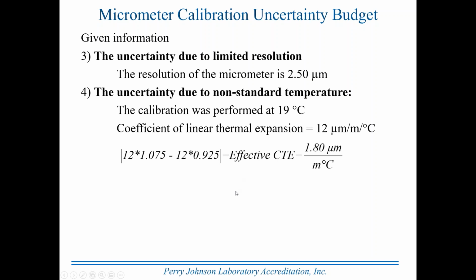Here's a formula that allows us to calculate what I refer to as the effective coefficient of thermal expansion. In other words, if we have 2 items that have different coefficients of expansion, let me say this too. The coefficient of thermal expansion itself typically is uncertain by plus or minus 15%. Some materials might only be 12%, some may be 17%, but it's typically considered as a 15% plus or minus uncertainty in the rate of expansion.